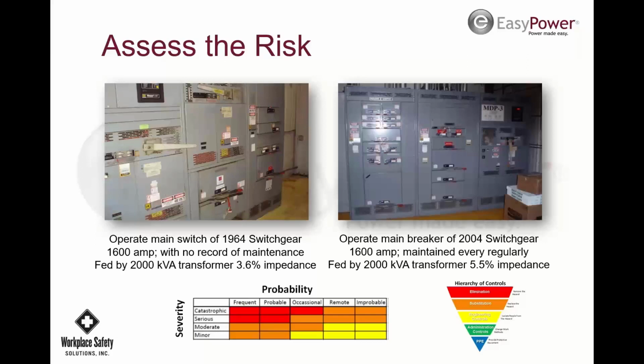So another question here: is there any electrical equipment that does not require arc flash analysis? Generally, when you're downstream, the arc flash studies generally go down to the panel level. They can go further, and we've done that. Some companies say let's go through, we want everything labeled, all disconnects and everything. Sometimes we get to a point where we can generically label at very low levels, and we color code our labels. So a green label would be generically low, less than 1.2 calories per square centimeter.